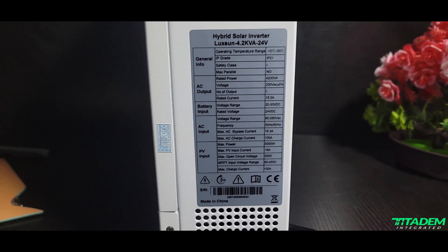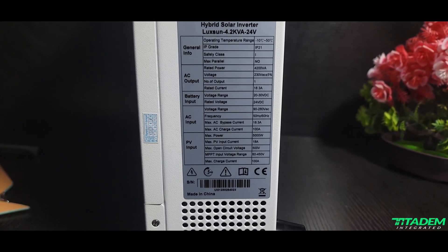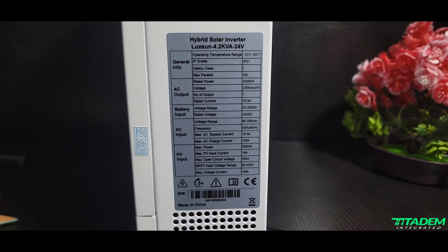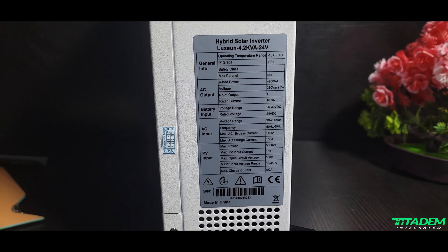Let's dive into the parameters. Temperature range is regular — minus 10°C to 50°C. IP rating is IP21, meaning it is meant for indoor use, not outdoor. Safety class is Class I — just insulation to prevent shock under regular circumstances. This particular one has no parallel capability. Rated capacity is 4.2 kVA. Voltage is 230V AC, output current is 18.3A. That means 18.3A × 230V equals 4.2 kW — so is this inverter 4.2 kVA or 4.2 kW? Since they say we can get up to 18.3A at the output, it should actually be 4.2 kW. Battery is 24V, and AC input range is 90V to 280V — though I wouldn't recommend that range; I usually stay within 170V to 250V.